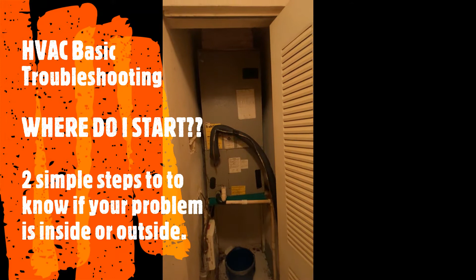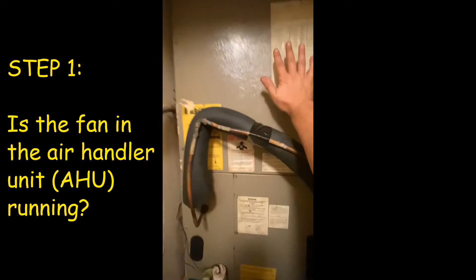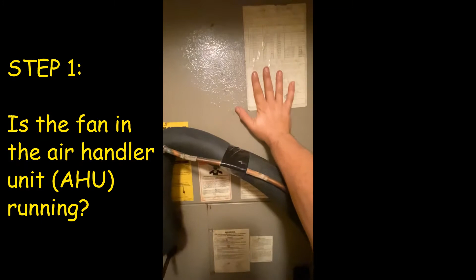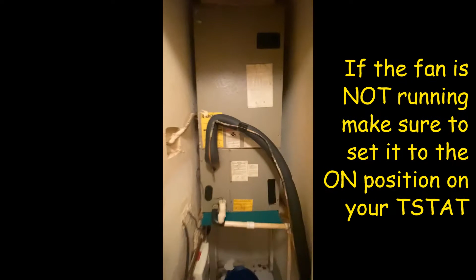Without any tools, just using our senses, we can learn a lot about what our unit is doing or isn't doing, with two simple steps. Step 1: go up to your air handler and see if you're moving air with your fan. Is your fan running? Sometimes it's a little quiet, so putting your hand there helps, but you can hear it most of the time. If you're not 100% sure, put your hand on there and you'll know - this fan's not running right now. So what do we do?